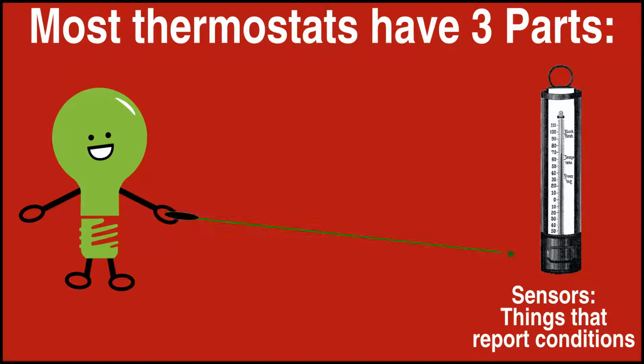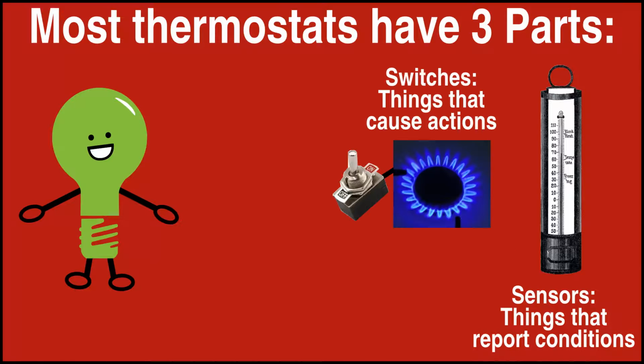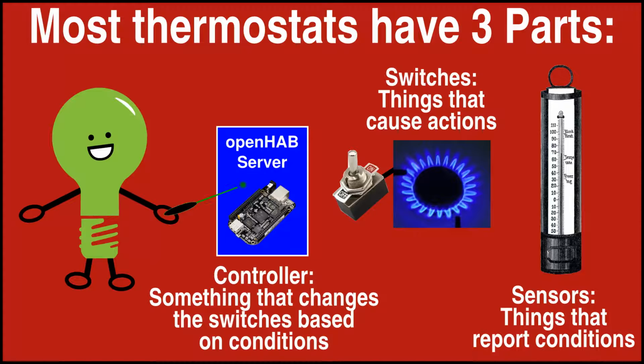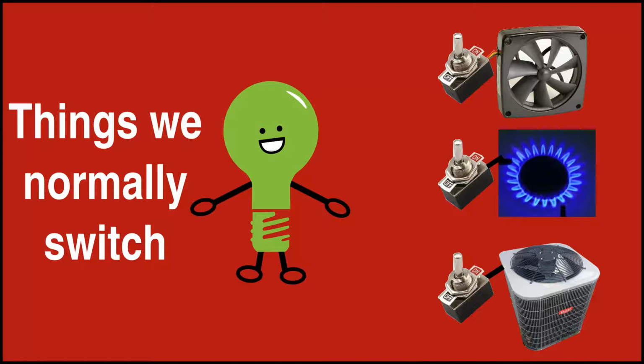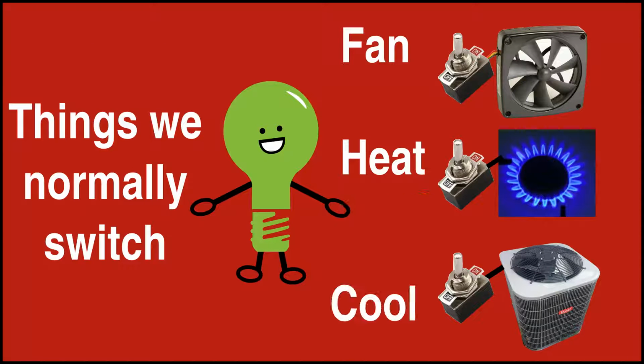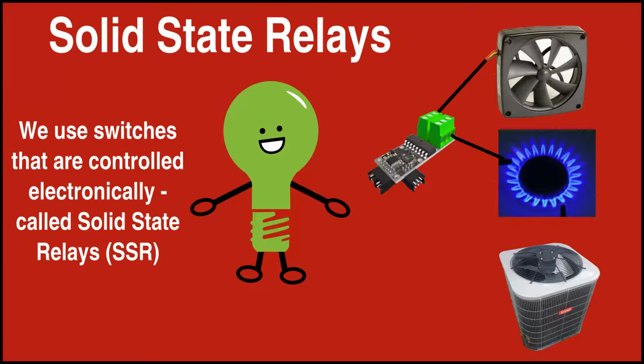Sensors are the first part of a thermostat and report conditions upon which the changes are made. The second part we refer to as switches. Switches cause actions, like turning the heat on or off. Finally, a controller is needed to change the switches based on conditions reported by the sensors. The things normally switched are fans, heating elements, and cooling elements. We use a special kind of switch called a solid-state relay. It is just a switch that can be controlled by an electrical signal. Each of our modules can control two devices.